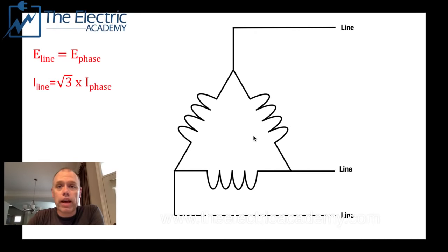Anybody that's worked in a plant knows that you have a ground fault detection system. That just indicates which phase it's on. Then you've got to go looking for it. I've done that. I've spent days trying to track down ground faults in a plant that I worked at, a styrofoam manufacturing plant, in fact. What else? They're really useful for distribution for that reason because you have three wires, not four, so you save some money on that.